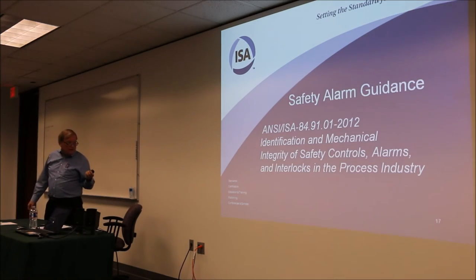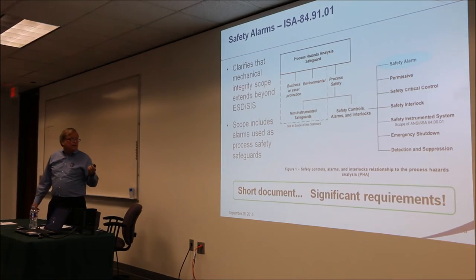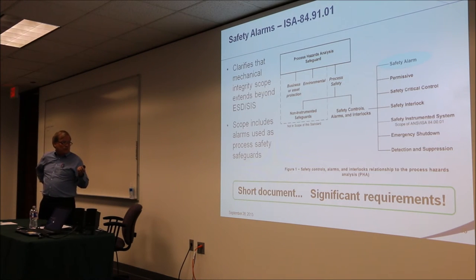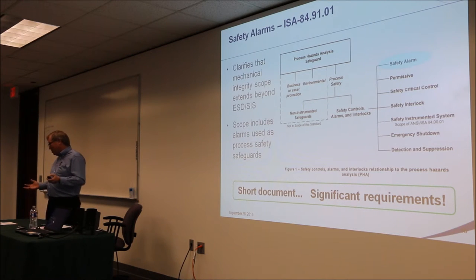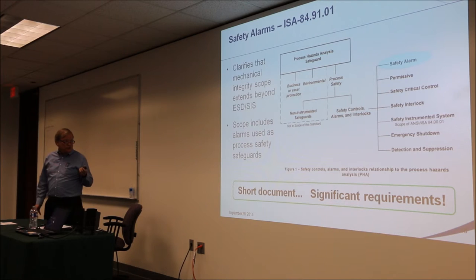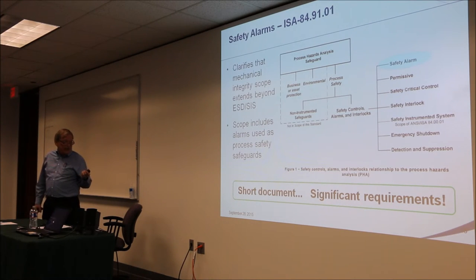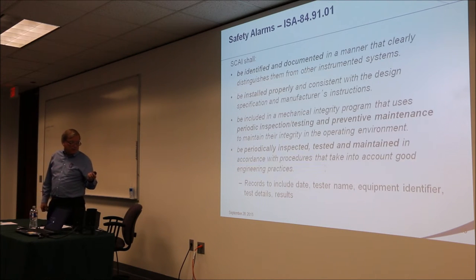Moving on to ISA 84.9101: the main intent of this standard was to clarify that safety instrumentation extends beyond SIS — any kind of control, alarm, or interlock where you're claiming risk reduction falls under this standard and needs to be in a mechanical integrity program. It's not a long document, but the requirements are important: you need a mechanical integrity program with testing, maintenance, best engineering practice for design and installation, and similar elements.